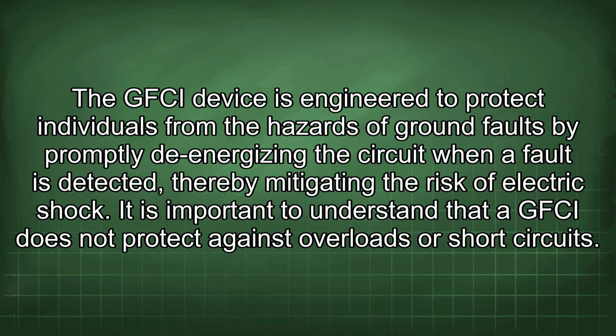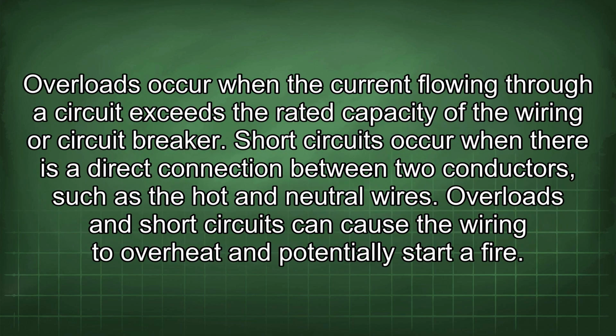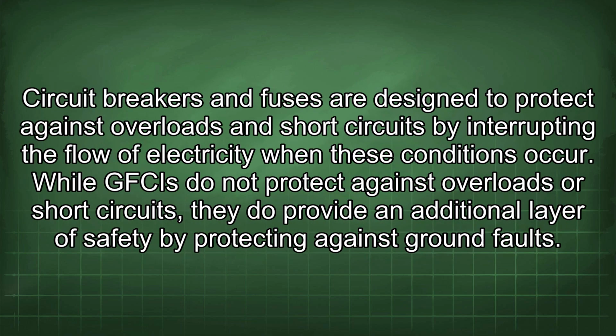It is important to understand that a GFCI does not protect against overloads or short circuits. Overloads occur when the current flowing through a circuit exceeds the rated capacity of the wiring or circuit breaker. Short circuits occur when there is a direct connection between two conductors, such as the hot and neutral wires. Overloads and short circuits can cause the wiring to overheat and potentially start a fire. Circuit breakers and fuses are designed to protect against overloads and short circuits by interrupting the flow of electricity when these conditions occur. While GFCIs do not protect against overloads or short circuits, they do provide an additional layer of safety by protecting against ground faults.